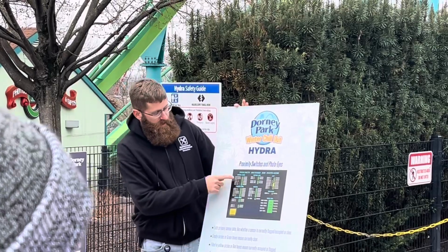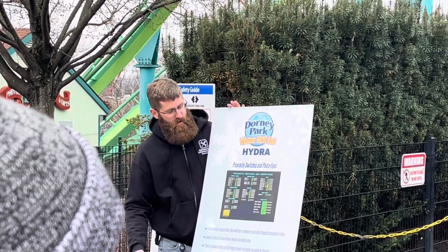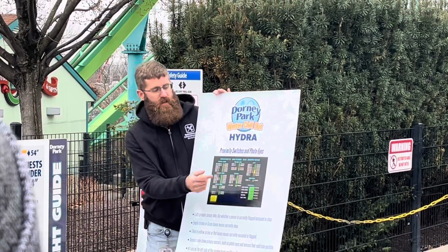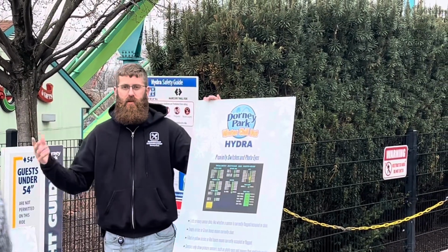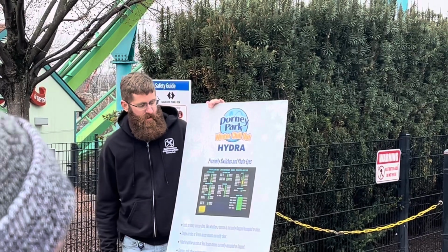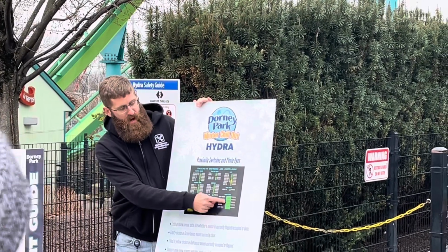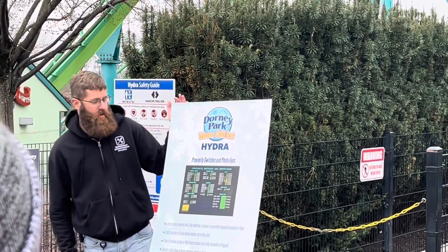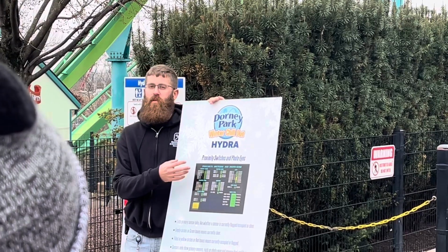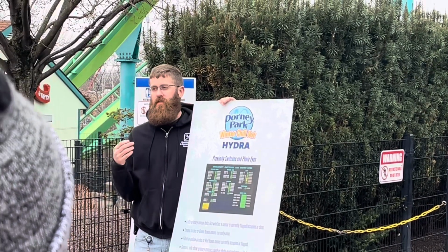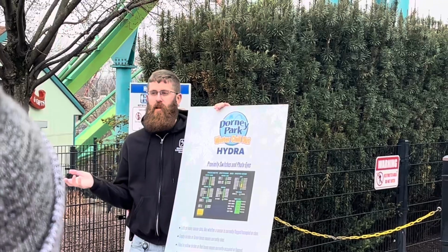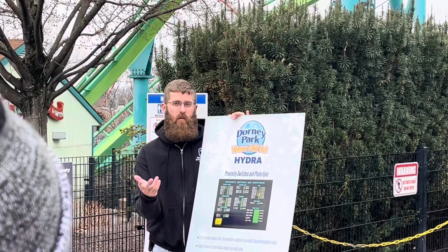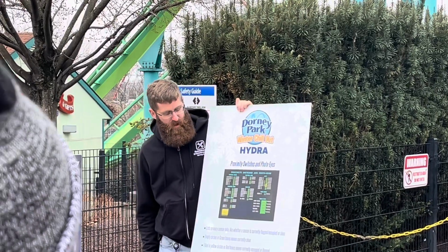So anything that's clear is blank, and then you have your two filled in yellow dots here. That just means those sets of contacts are giving input back to the PLC at that time. Your photo eye blocks, again, they'll be red if they're flagged and green if they're clear. This screen is good for trying to help determine if you have a bad sensor. Like if one is flagged all the time, the dot will appear yellow all the time, even if it shouldn't be. Or in this case, this one would be off because it's normally on. So that's kind of what we use this screen for.